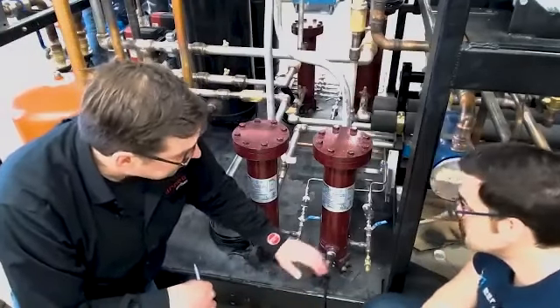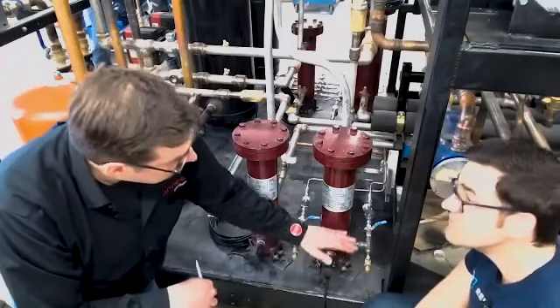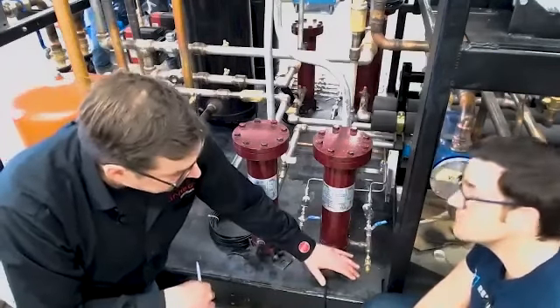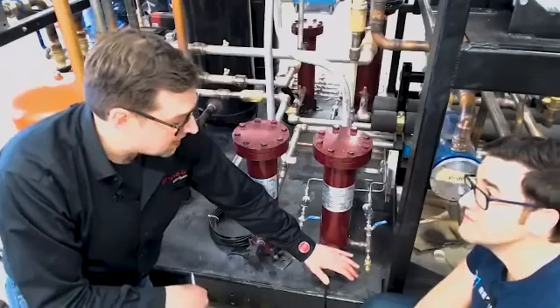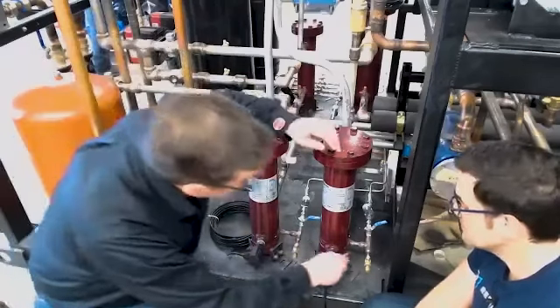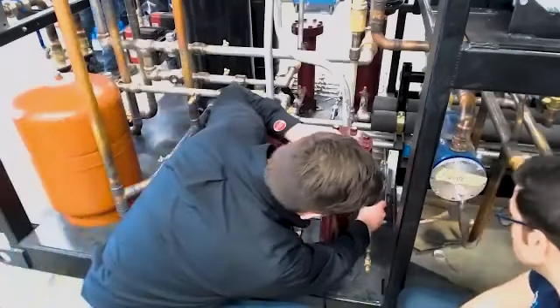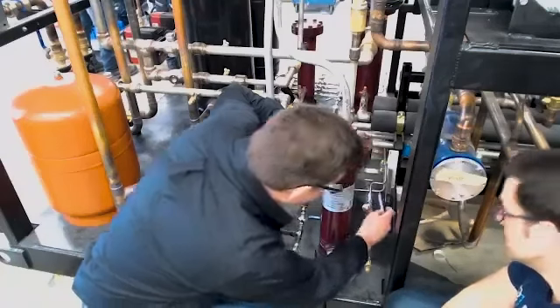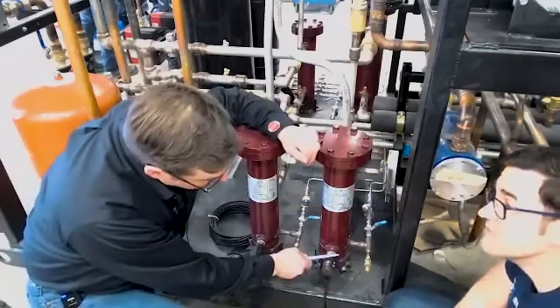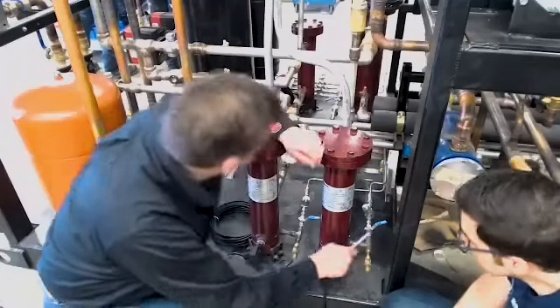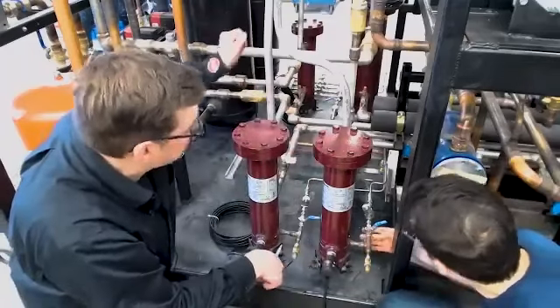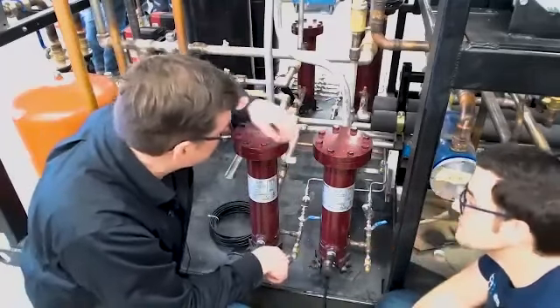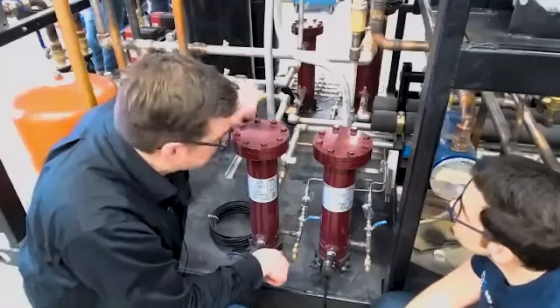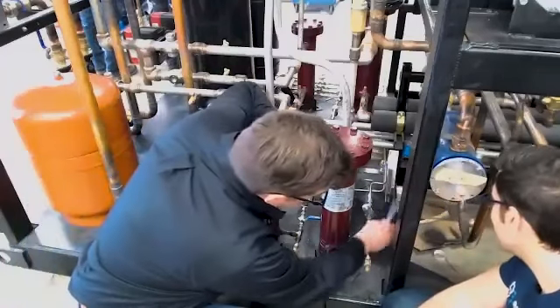So, common havoc in the field. If you're filling up with oil, start by taking a look at your optic eye. Is your optic eye calling? Or we're going to get down to the line here. Is your check valve not opening properly? Yeah. So as this calls for oil, essentially what we're doing is we've created a huge pressure differential. We're going to siphon oil. We're going to suck oil into our oil reservoir. We have a dedicated shut-off valve here.